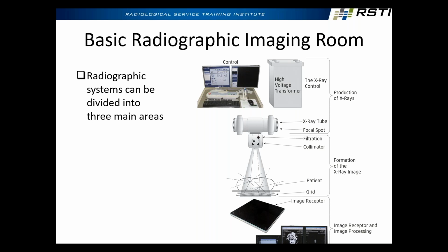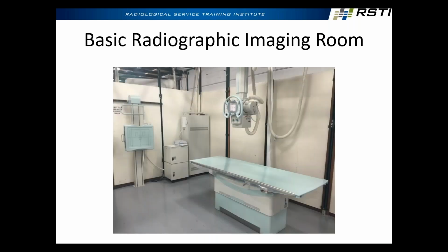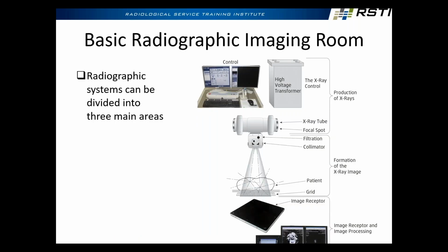When they talk about the X-ray generator, what do you think of? If I told you to check the generator, what would you expect me to have you look at? What's that? Well, that's what it is, but yeah, you typically, when somebody says check the generator, well, the generator itself is actually the high voltage transformer, right?